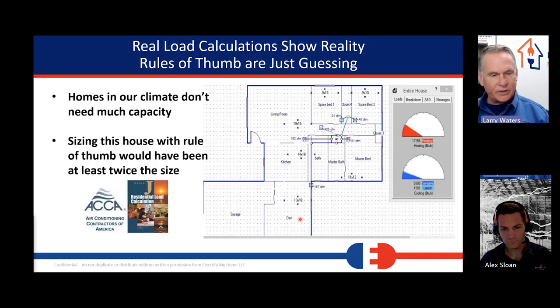We started doing load calculations, and we started understanding that every system we were installing was too big. You can't go into a house from the 1970s where we said 400 square feet per ton, and the people put new windows in, insulation in, they've tightened the house up in various ways. They now have shade and shade structures and all these things around their house that have grown in, and still say it's 400 square feet per ton. You can't do that. So the only way that you can know, based on everything that's been done to the house or you're going to do to it, is to do a load calculation. It's really the only way to do it.